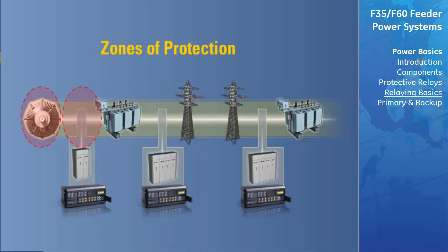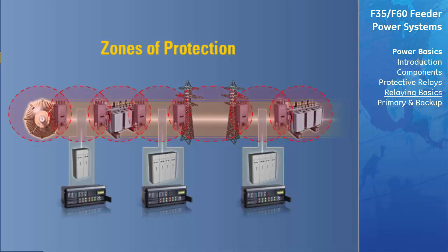One of the protection engineer's most powerful tools is the concept of zones of protection. The boundary of a protective zone represents the region that a particular protective element covers, and it is necessary for these zones to overlap to ensure proper protection. If two zones did not overlap and a fault occurred at the boundaries, no relays would be tripped. For failures within the overlap area, more breakers will be tripped than needed, but the overlap areas are relatively small and the probability of failure in this region is very low.